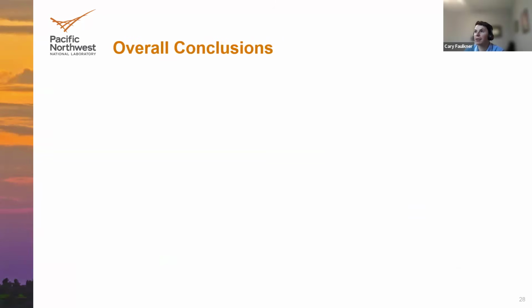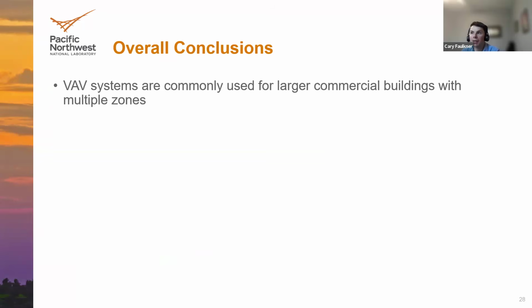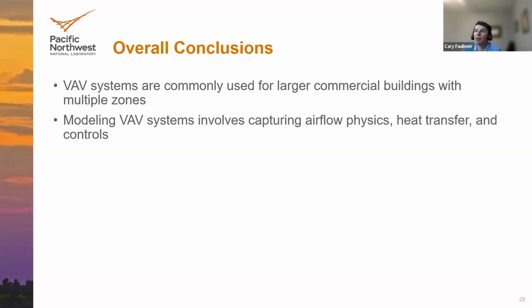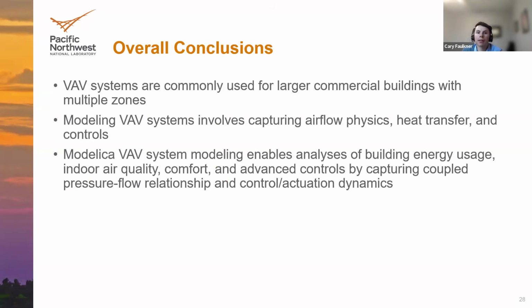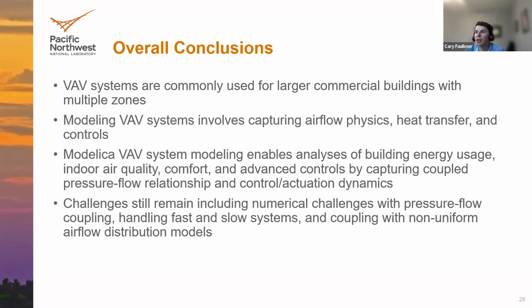So now I've gone through my presentation and just want to talk about some overall conclusions. As introduced, these VAV systems are commonly used for larger commercial buildings with multiple zones. They can be more energy efficient and control varying temperatures among zones better. To model the VAV system, there are several key aspects we want to capture, including the airflow physics, heat transfer, and controls. Modeling these systems using Modelica enables analyses of building energy usage, indoor air quality, comfort, and advanced controls, including capturing the coupled pressure-flow relationship as well as the control and actuation dynamics.